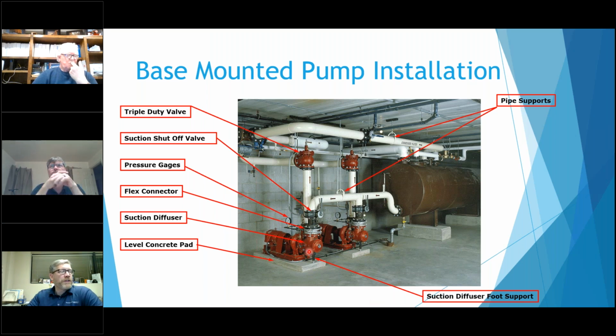On our pumps, there is a tapping on the suction flange as well as right at the discharge nozzle. You just remove the pipe plugs and you can put some pipe right into it and get your pressure gauge there. There's also some built into the suction diffuser as well, so you don't have to actually put T fittings in or a connection into the pipe. It's already built right into the pump.